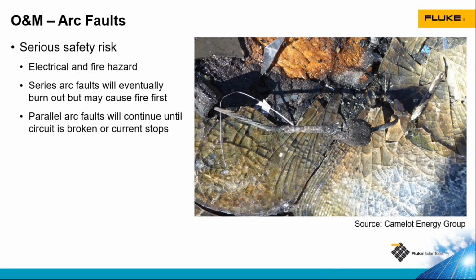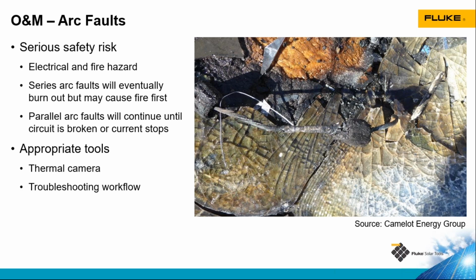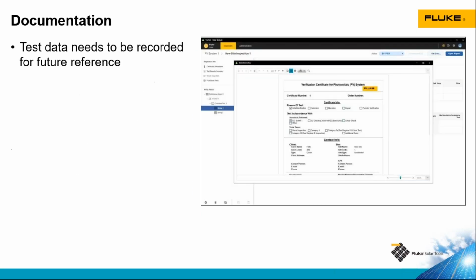The picture on this slide, this used to be a connection between two modules like we saw in the last picture. The left-hand side was not plugged all the way into the right-hand side, which led to a high resistance connection that arced and over time eventually burnt out and caused a fairly significant fire on this commercial roof. We can use thermal cameras, we can use troubleshooting workflows to do that inverter procedure I talked about to find arc fault locations.